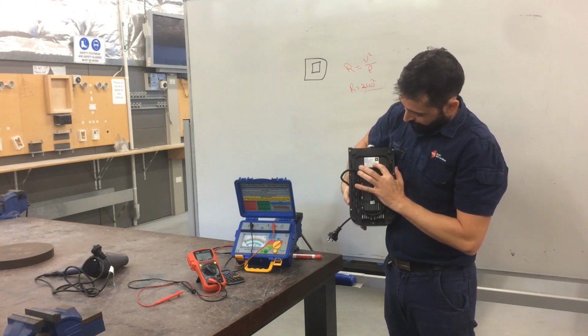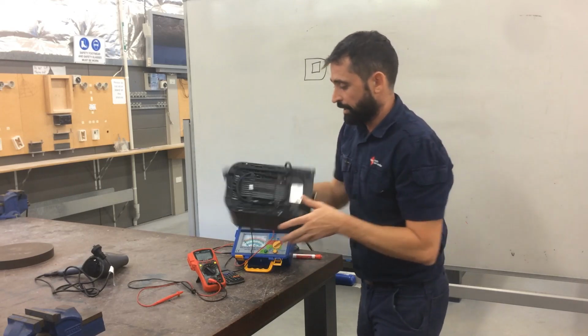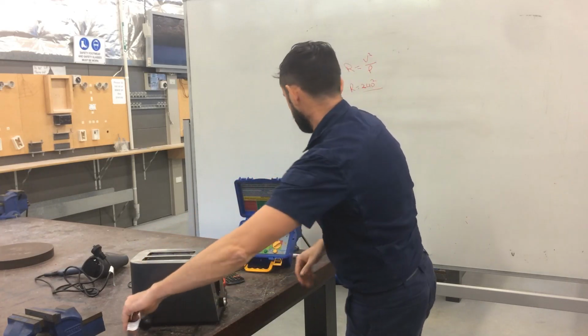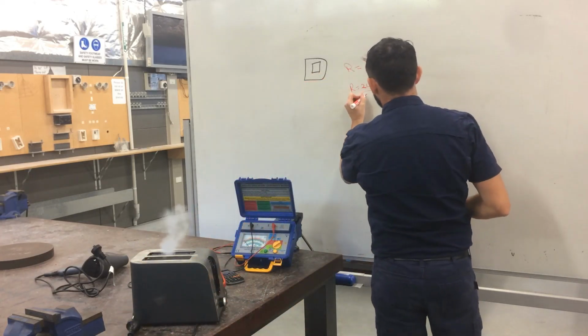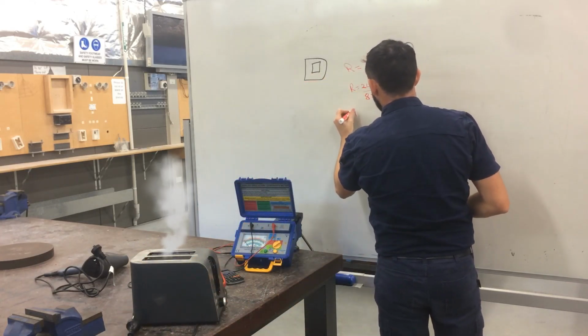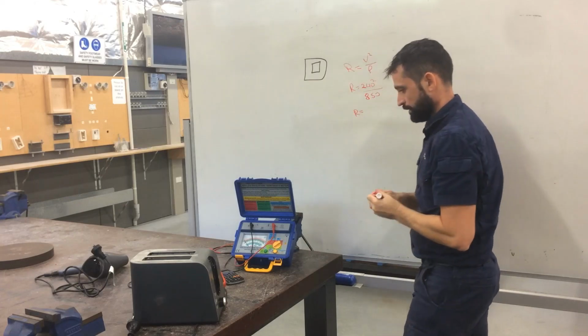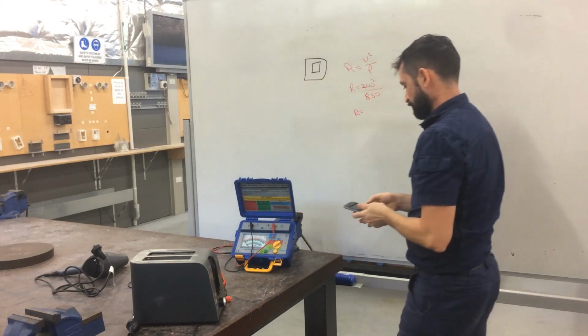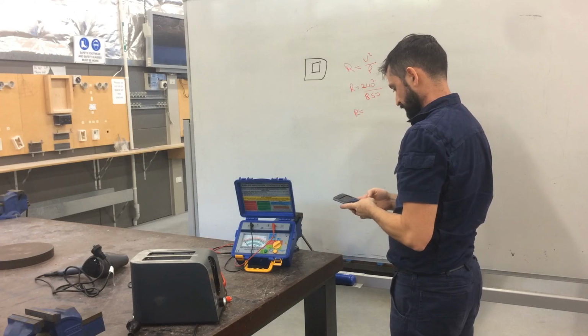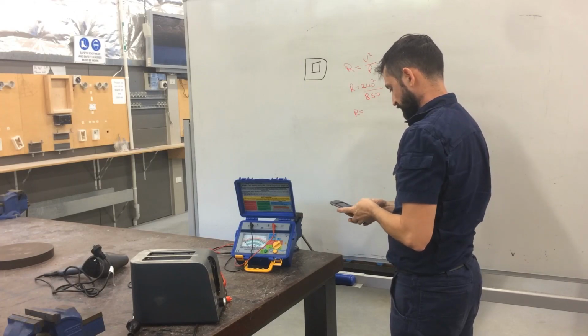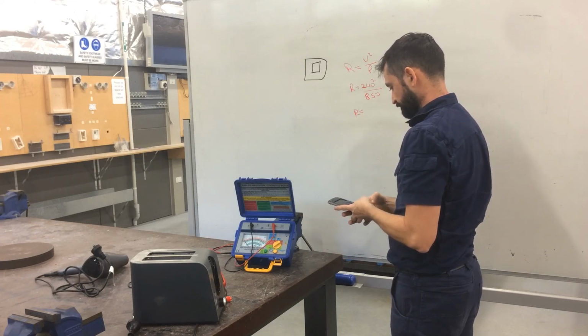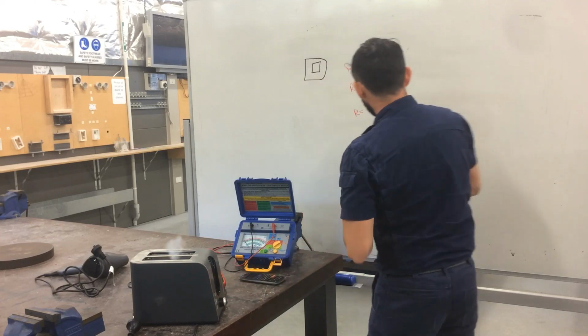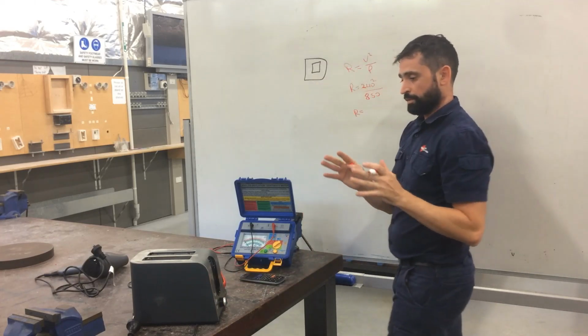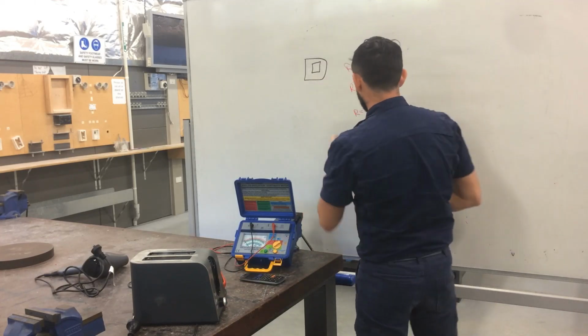Now, the manufacturer tells us it's going to be 850 watts. So we now put that into our equation: R equals 240 squared divided by 850. If it's functioning properly, we should get a resistance of 67 ohms.